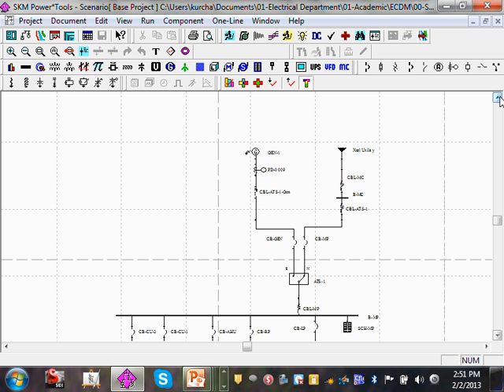So that's the voltage. The second thing is the trip, they call it long time pickup for the circuit breakers. If you have a 100 amp continuous load multiplied by 1.25, you get your 125 amp. Here's a 125 amp circuit breaker. Done, check. That's the second thing for a circuit breaker, voltage and current. A lot of us guys are very familiar with this. The third thing is the interrupting rating. And that's what a lot of electricians probably don't deal with too much. The interrupting rating is about a short circuit and ground fault condition. If you have a short circuit, how much current can this circuit breaker handle before it turns into pieces, like you have seen? That one becomes a big deal.